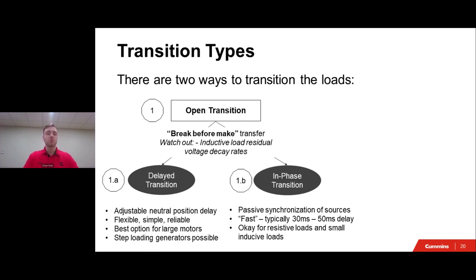In an open delay transition, when switching from the normal source to an emergency power source, the automatic transfer switch will pause. That delay typically lasts for a specific preset amount of time or however long it takes the load voltage to drop below a pre-specified level. Now, this requires a three-position transfer switch like I discussed earlier. This is due to the fact that the three-position transfer switch allows for the automatic transfer switch to go into that center off or neutral position. So when you do have that delay, say the normal power source fails, you have a delay built in, the transfer switch will then switch to that center off position. Once your delay has gone past, it will then switch on to your emergency power source.